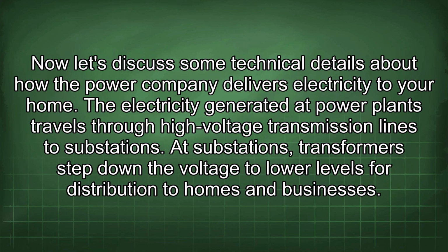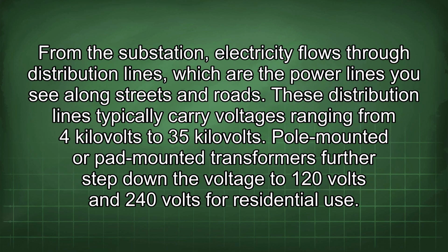Now let's discuss some technical details about how the power company delivers electricity to your home. The electricity generated at power plants travels through high voltage transmission lines to substations. At substations, transformers step down the voltage to lower levels for distribution to homes and businesses. From the substation, electricity flows through distribution lines, which are the power lines you see along streets and roads. These distribution lines typically carry voltages ranging from 4 kV to 35 kV. Pole-mounted or pad-mounted transformers further step down the voltage to 120 volts and 240 volts for residential use.